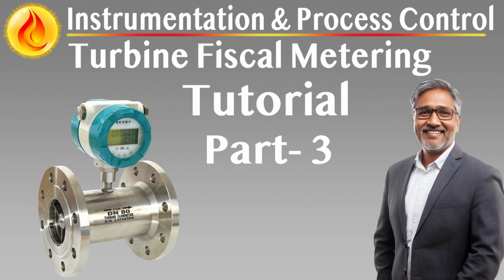Turbine meters are the core primary measurement element of the fiscal metering system. Their selection, calibration, and installation must ensure traceable, reproducible accuracy under actual process conditions. Each meter must be matched not only to flow and fluid properties, but also to system-level diagnostic requirements, enabling continuous verification and real-time performance assurance.